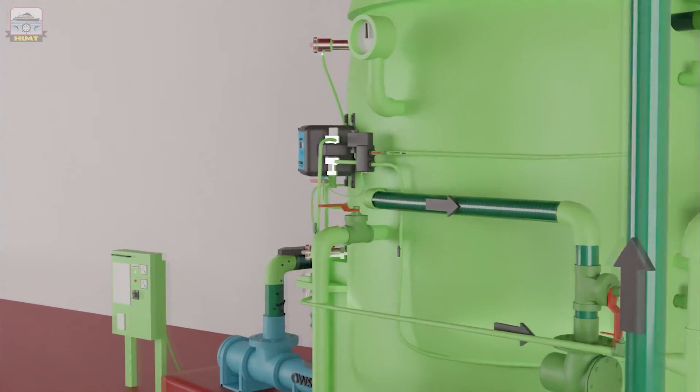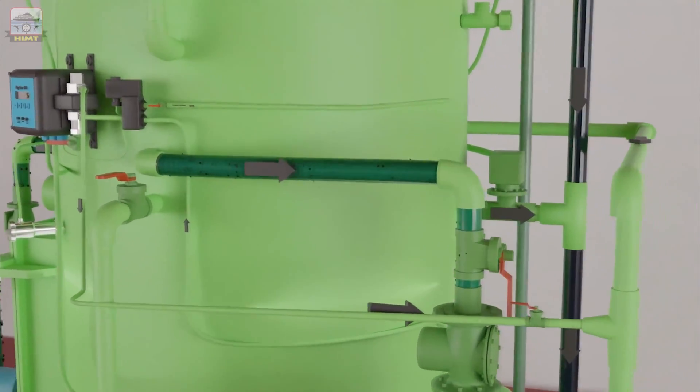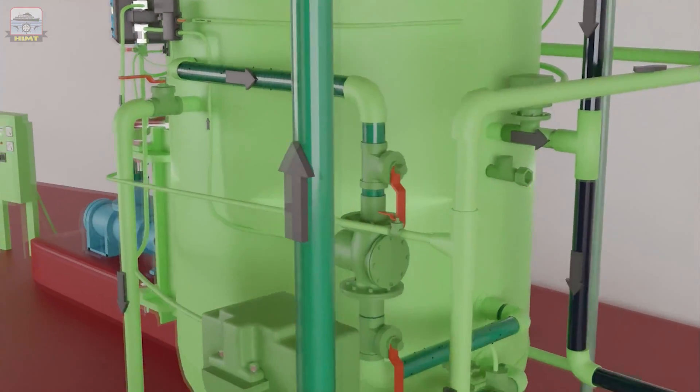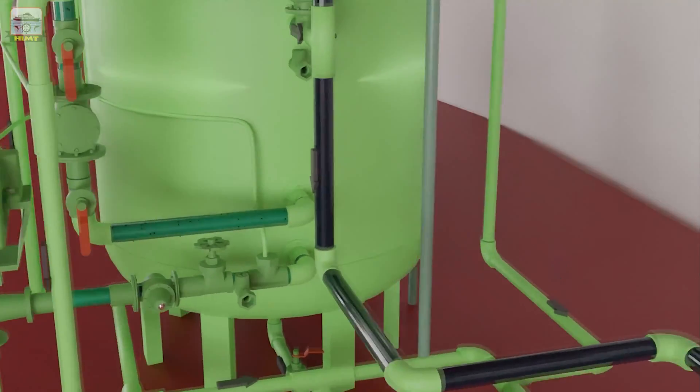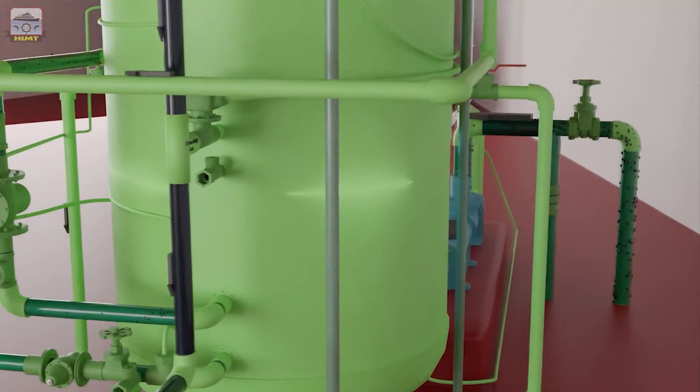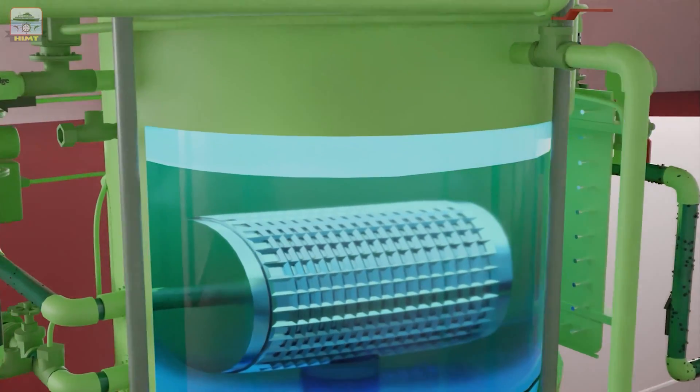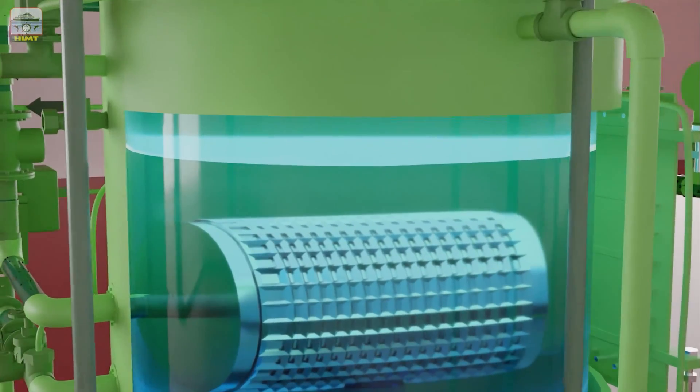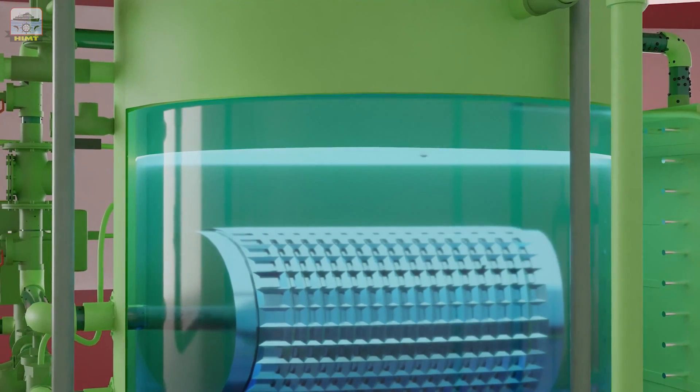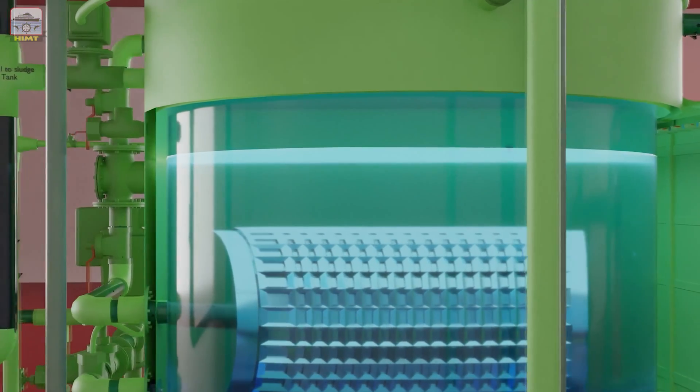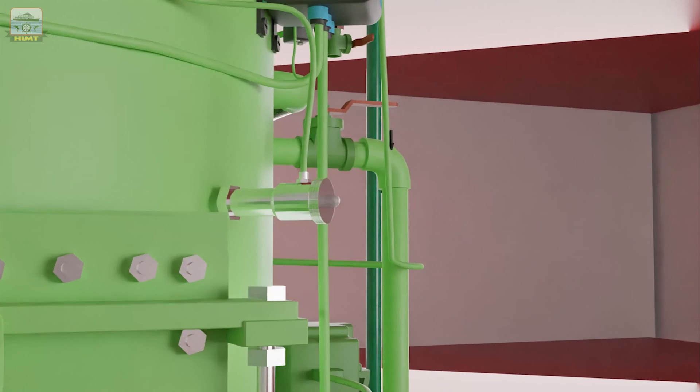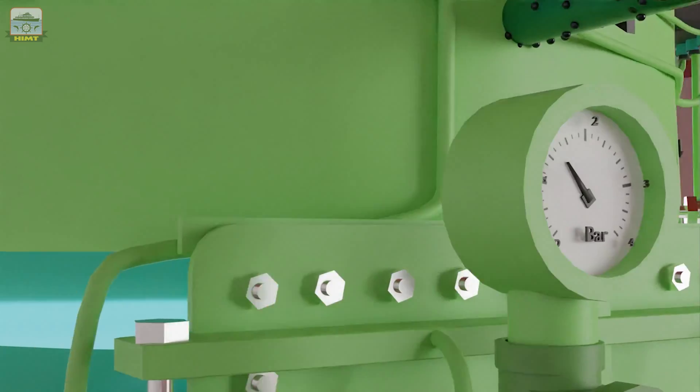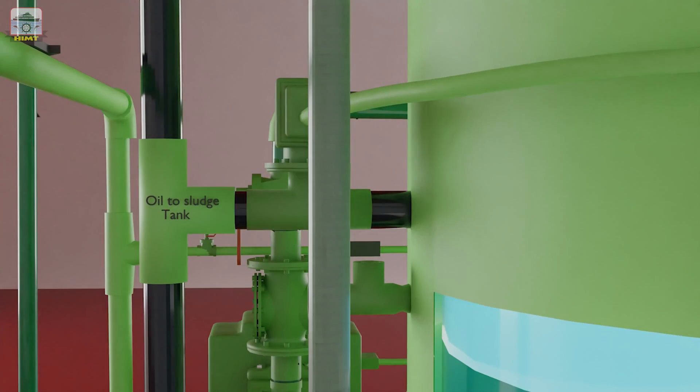Now, we can see what is happening in the secondary chamber. In the secondary chamber, we can see the globules of oil and the finer oil particles, which were not separated in the primary chamber, rise and collect on top. When the oil level probe detects oil, it opens the oil discharge valve, directing oil to the sludge tank.